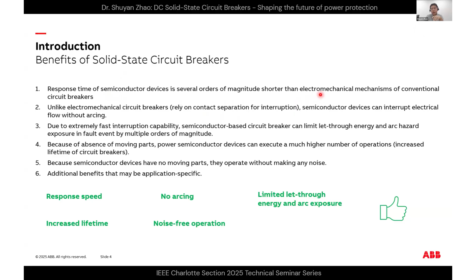First, of course, is response time, the main benefit of solid state semiconductor devices. It's several orders of magnitude shorter than electromechanical conventional technology. Conventional circuit breakers typically have response times at the millisecond or hundreds of milliseconds level, which is very slow for a DC system.